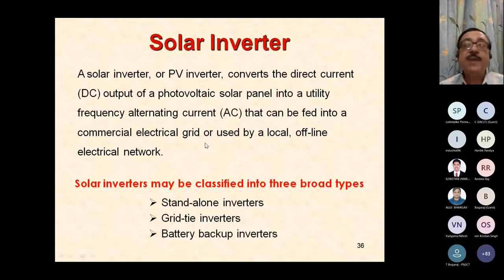Both are possible. You can have a local load, or you can feed it into the grid, or you can have both. Based on that, solar inverters may be classified into three broad types. First, standalone inverters, where there is no real power connection with the grid. You have a solar system and a local load, maybe my house. I have a solar panel and I'm using it for a house. My house is located in a remote area, far away, where there is no electrical supply. That's an example of a standalone inverter.